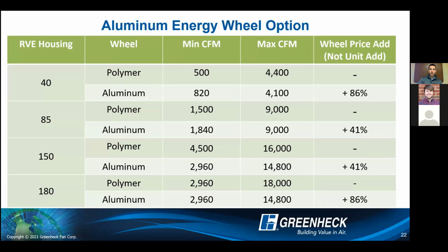So from an aluminum energy cost add, I want to really quickly add that this column on the right is wheel price only. So it's not the unit itself add. It's not saying with the aluminum energy wheel, it's going to be an 86% cost add to utilize those aluminum energy wheels, but the wheel specifically that's going in there will be an 86% or 41% cost add, depending on the housing size. And generally the wheels are about 5 to 10% of the cost of the overall unit itself. So it does add up.